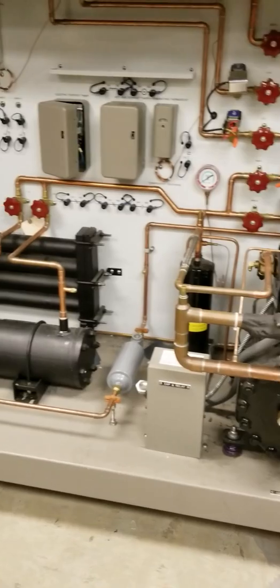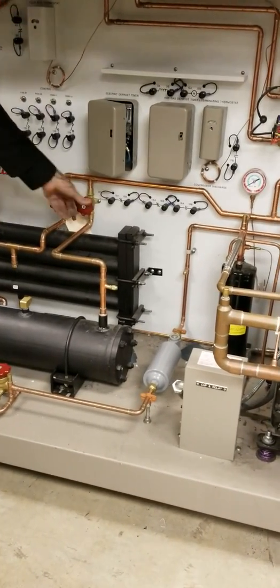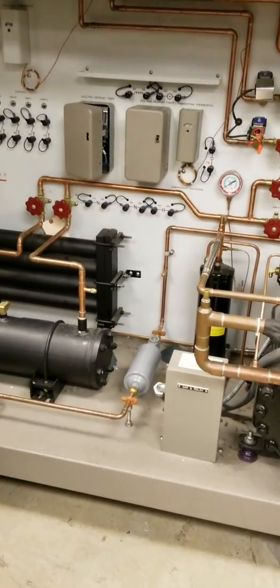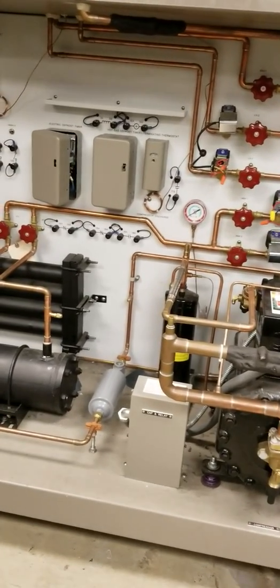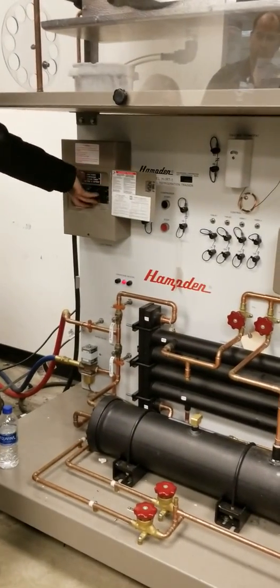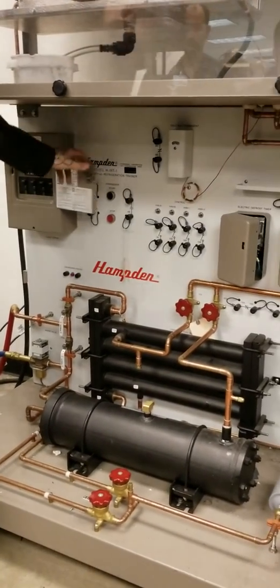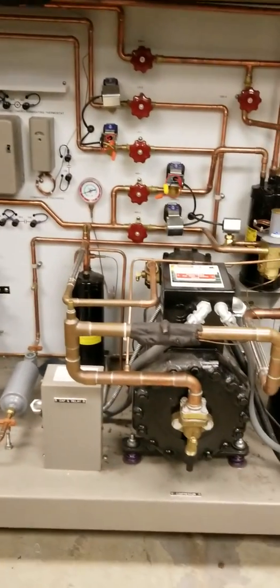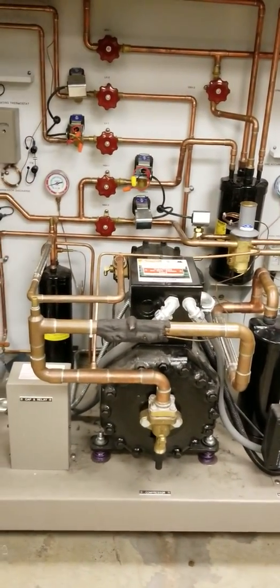Now that we know everything's going, we don't know what our valve positions are, but we can watch our pressures and see what it does. If it goes off on high pressure, here's an example. Let's turn it on. Compressor's on. Let's watch our high side pressure.